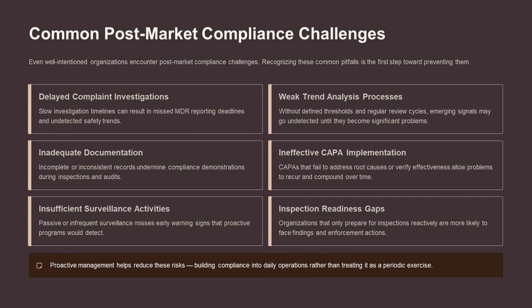Even well-intentioned organizations encounter post-market compliance challenges. Recognizing these common pitfalls is the first step toward preventing them. Delayed complaint investigations can result in missed MDR reporting deadlines and undetected safety trends. Weak trend analysis processes, without defined thresholds and regular review cycles, mean emerging signals may go unnoticed until they become significant problems. Incomplete or inconsistent records undermine compliance demonstrations during inspections.